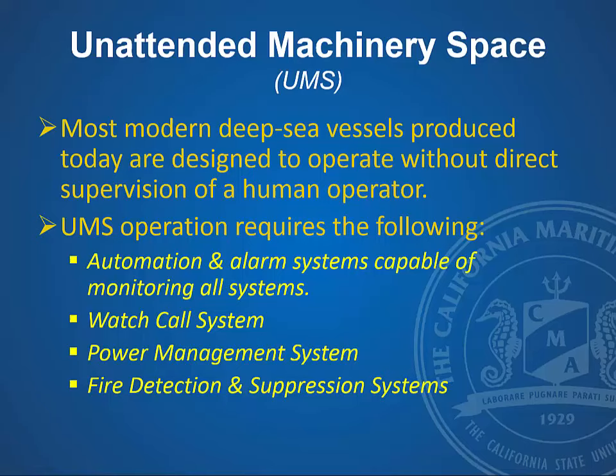Under UMS operation, you have to have automation alarm systems capable of monitoring all your major systems. You have a watch call system where you can select which engineer is on call, so that if there's an emergency, it will notify that engineer of what alarm has occurred, so that engineer can come down into the engine room and respond to it. If the watch engineer does not respond to the watch call system, then it will typically notify the bridge and the chief engineer that the engineer failed to respond to the watch call. You also have to have a power management system and fire detection and suppression systems. All have to be in place for unmanned status.